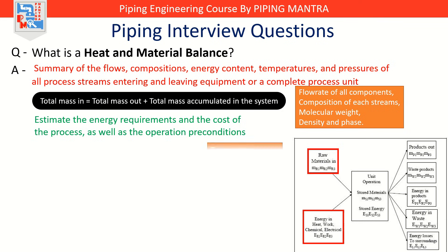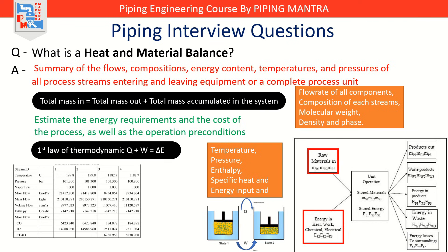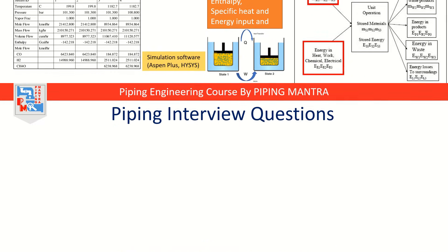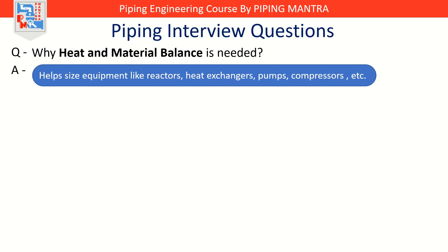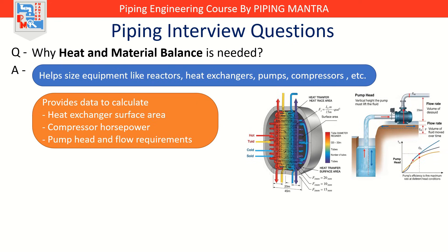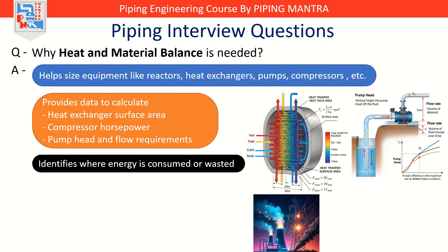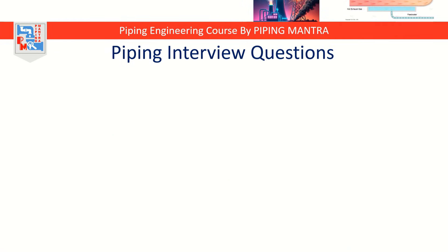In heat balancing, we look at temperature, pressure, enthalpy, specific heat, and energy input and output for equipment like coolers and reactors. Heat balance is calculated based on the first law of thermodynamics: Q + W = ΔE. It is typically presented in a table format, often used with process simulation software like Aspen Plus. Heat and material balance is needed because it ensures all mass and energy flows are accounted for, helps size equipment like reactors, heat exchangers, pumps, and compressors, provides data to calculate heat exchanger surface area, compressor horsepower, pump head and flow requirements, and identifies where energy is consumed or wasted — helping optimize steam usage, cooling loads, and waste heat recovery.